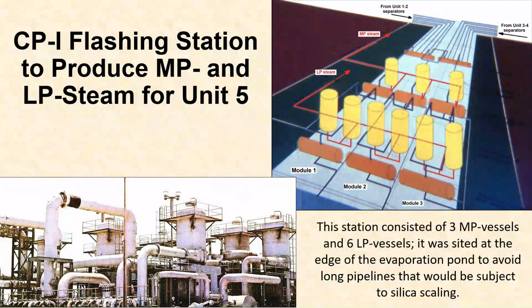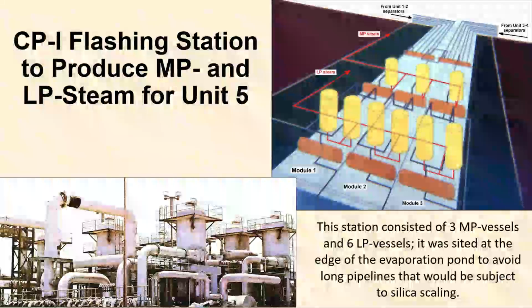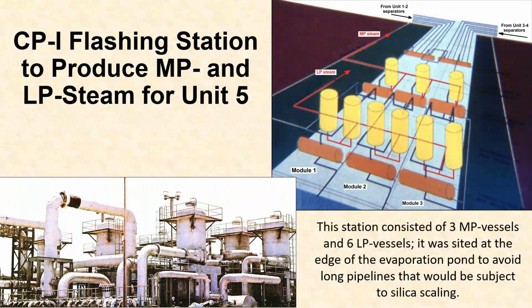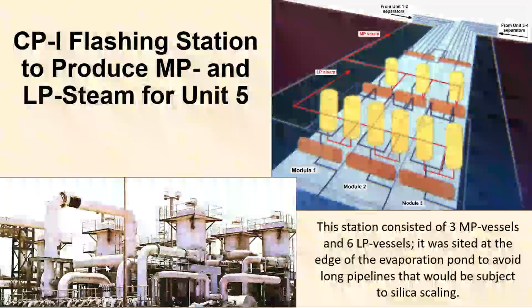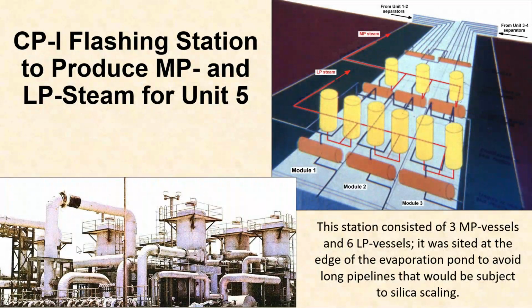Okay, unit number 5 required that all of the liquid being separated at all the wells be conveyed through pipes to a central location, a flashing station. It was done, as you can see in the schematic, by first sending that pressurized liquid to a first bank of flashers. These are the medium pressure flashers that produce steam, which was then sent back to the unit, the powerhouse. The liquid from the first phase of separation went down to 2 other additional flashers, 2 for each of those, and produced the low pressure steam and sent that to the powerhouse. The remaining liquid, which is now highly supersaturated in silica, is collected and immediately dumped into the evaporation pond. So this is the picture of the units with the medium pressure separators in the front, and the 6, you can only see a few of them in the back. Next slide, please.